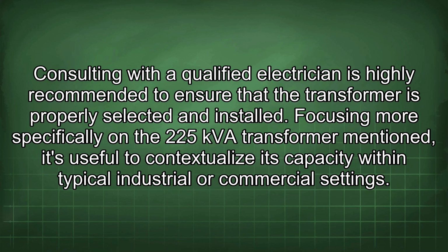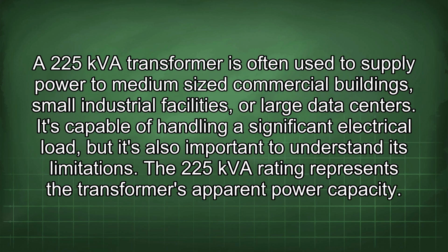Focusing more specifically on the 225 kVA transformer mentioned, it's useful to contextualize its capacity within typical industrial or commercial settings. A 225 kVA transformer is often used to supply power to medium-sized commercial buildings, small industrial facilities, or large data centers. It's capable of handling a significant electrical load, but it's also important to understand its limitations.